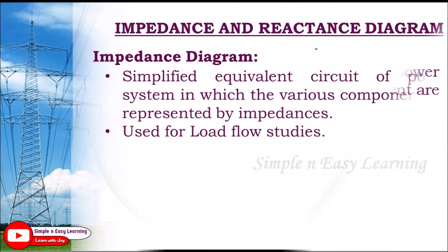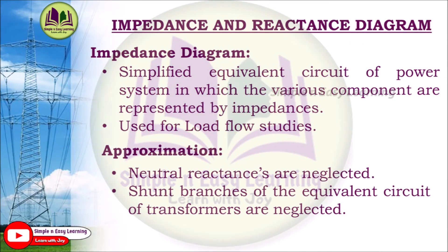An impedance diagram is a simplified equivalent circuit of a power system in which the various components are represented by impedances. The impedances consist of resistance and reactance, represented as R plus Jx, giving impedance Z. We represent a single line diagram in terms of an impedance diagram, where x represents inductive or capacitive reactance. This impedance diagram is used for load flow studies, also called power flow studies.